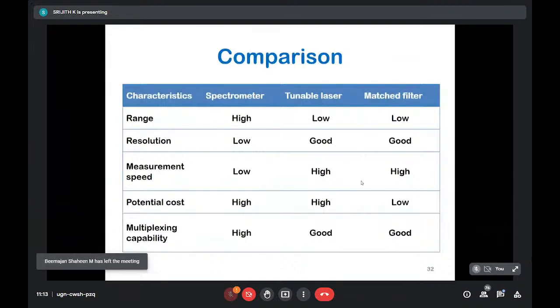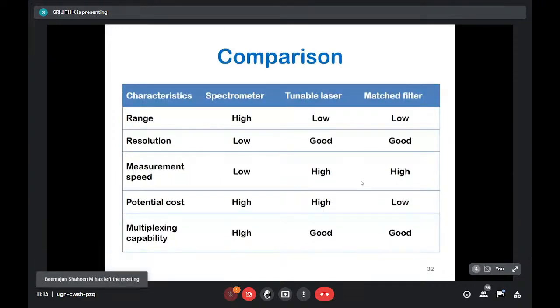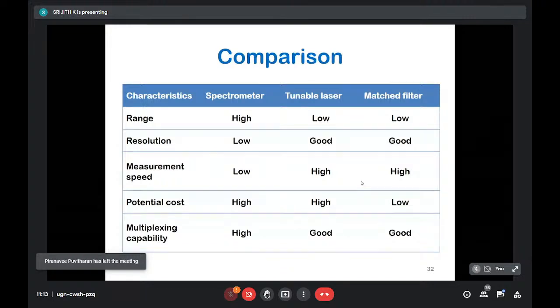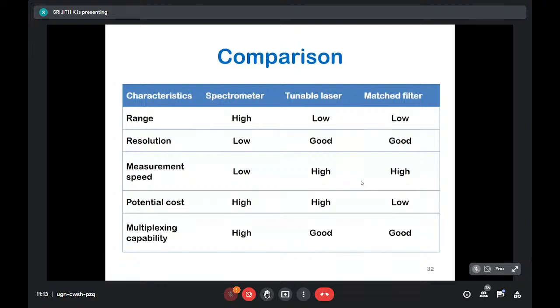Okay, so here's the comparison in terms of range, resolution, measurement speed, cost, and multiplexing capability. As I told you, the highest range is offered by the spectrometer. Why do I say that range is lower for the other two? Because in both the other two cases, you are utilizing the reflection slope of the FBG, and the typical reflection width of the FBG is something like 0.2 to 0.3 nanometers. So it's pretty low.